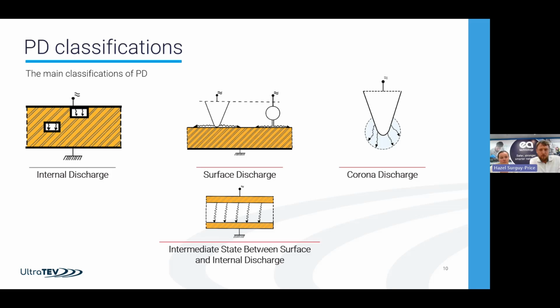The final category is corona discharge. This is discharge to air. If anyone's walked under an overhead line on a wet day, you'll have physically heard this, and probably had to see it in extreme cases. In certain situations, you'll hear a lot of people say this doesn't matter. And that's true. If it's there in some of the outdoor yards, etc., you won't pay that much attention to it. But if it's in an enclosed environment, it has secondary issues. If you're seeing corona discharge going on in the cable box or in a sealed environment, that will lead to byproducts being produced that will actually corrode the box itself and the metalwork around it, and so there'll be a secondary failure.